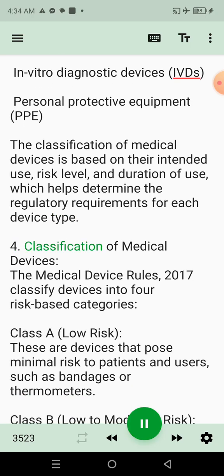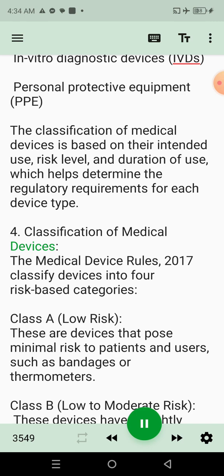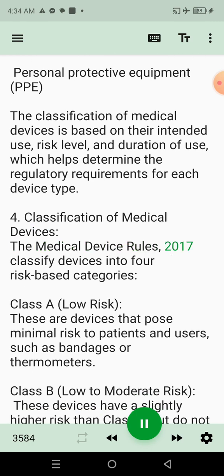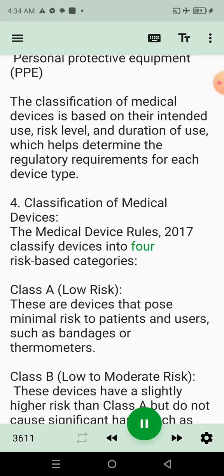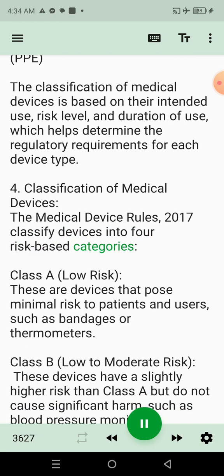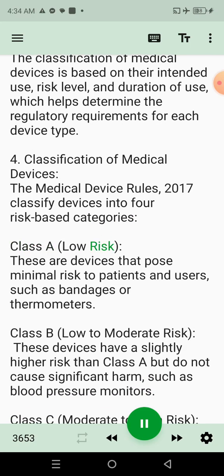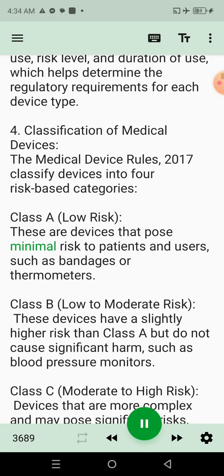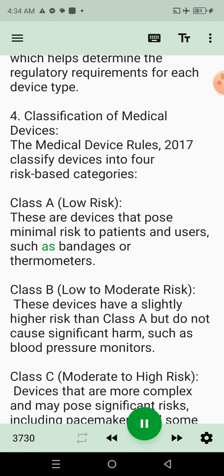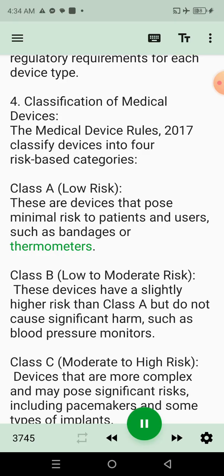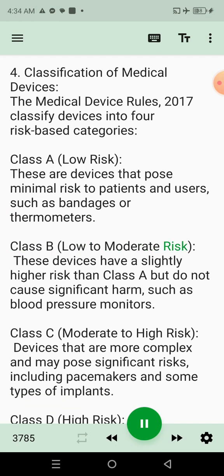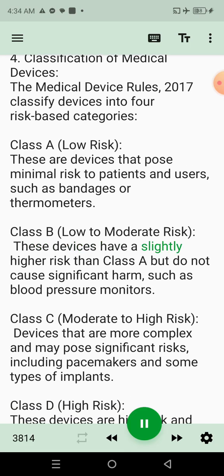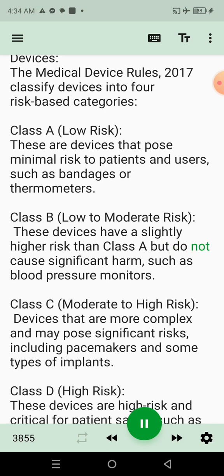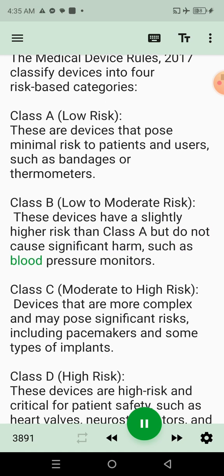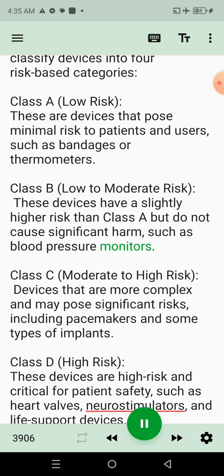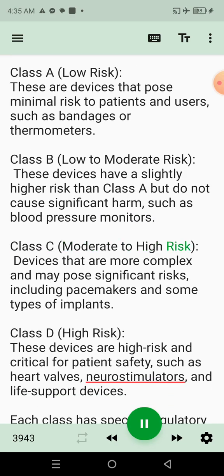4. Classification of medical devices. The Medical Device Rules, 2017 classify devices into 4 risk-based categories. Class A, low risk. These are devices that pose minimal risk to patients and users, such as bandages or thermometers. Class B, low to moderate risk. These devices have a slightly higher risk than Class A but do not cause significant harm, such as blood pressure monitors. Class C, moderate to high risk.